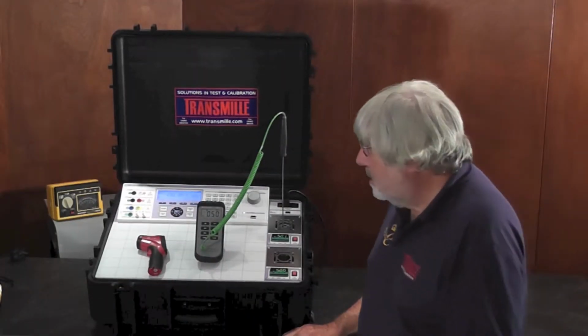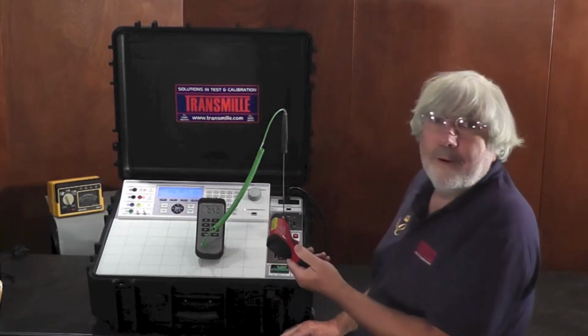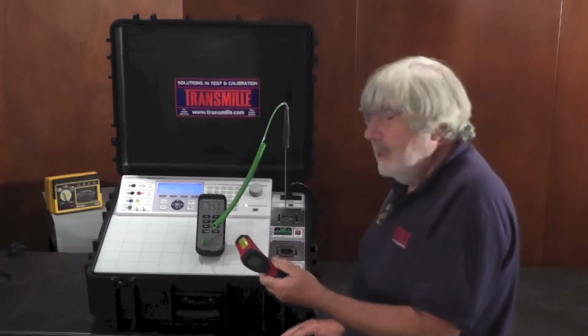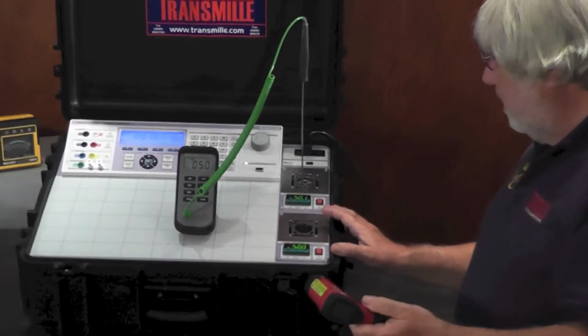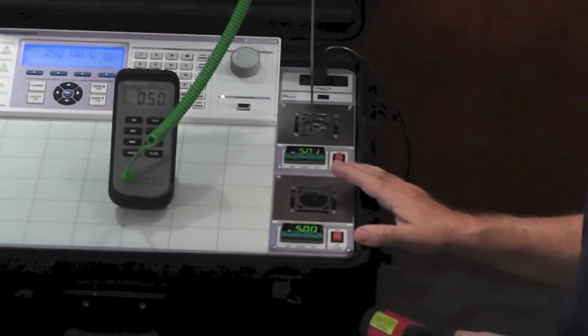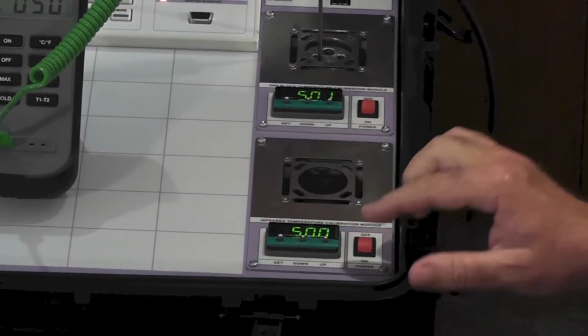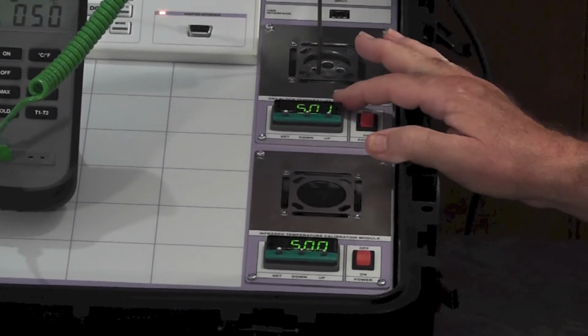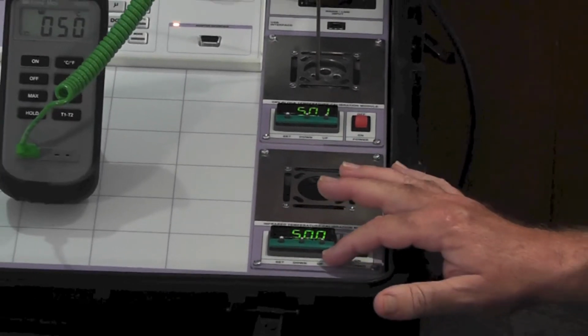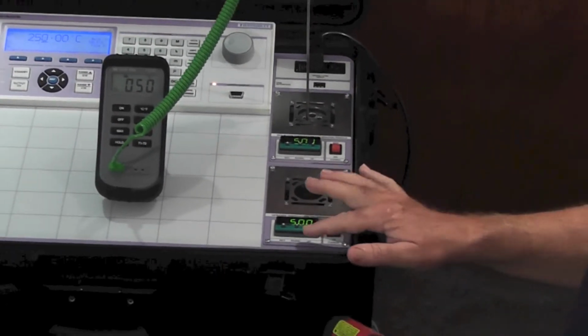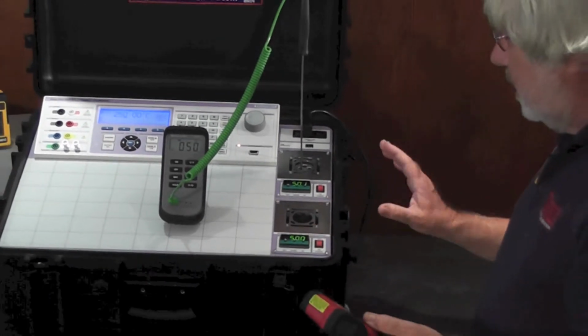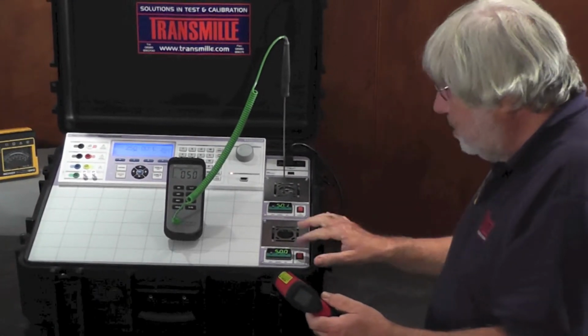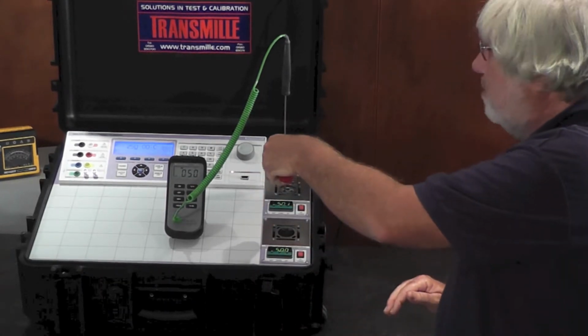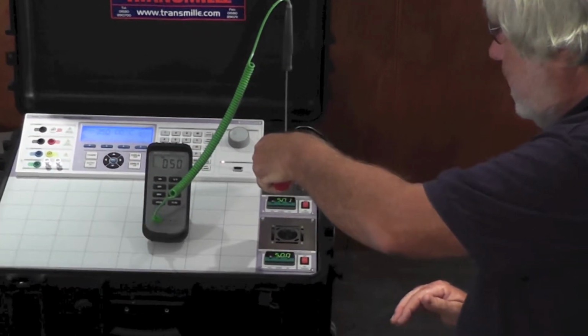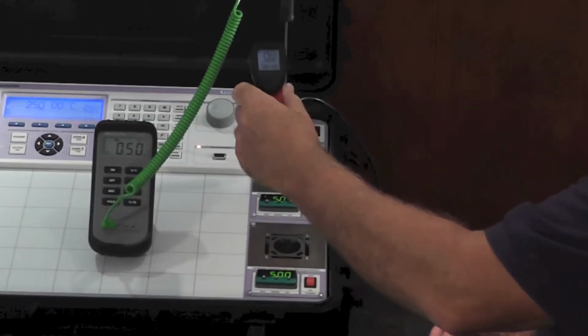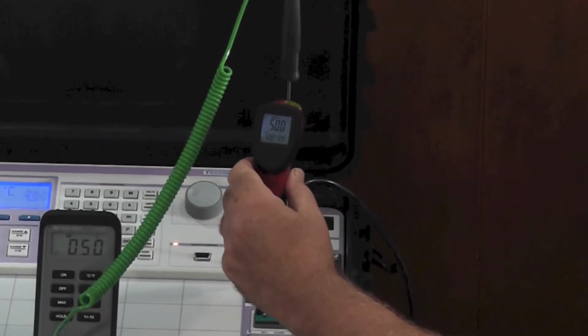The calibration of infrared thermometers, very popular these days, is just as simple as temperature probes when you have the infrared temperature calibration module fitted. Simply set your temperature. It's the same kind of controller exactly as used for the dry block calibrator. So it's just an up-down control to set whatever temperature you wish to use. I have it set to 50 degrees here. Just leave it for a few minutes to stabilize. When you see the temperature is stabilized, take your thermometer and point it at the target. And there we can see the 50 degrees.